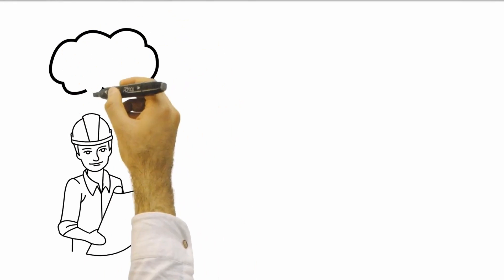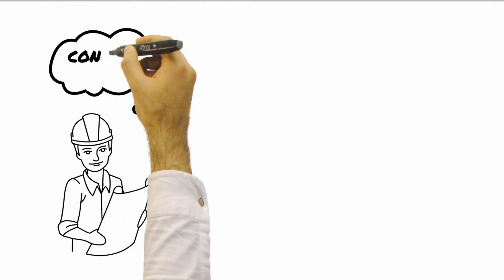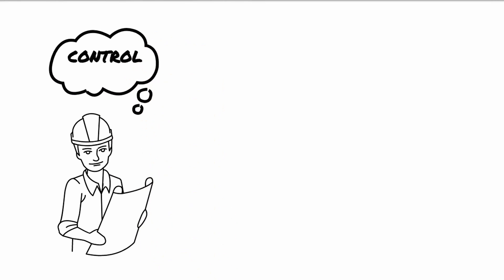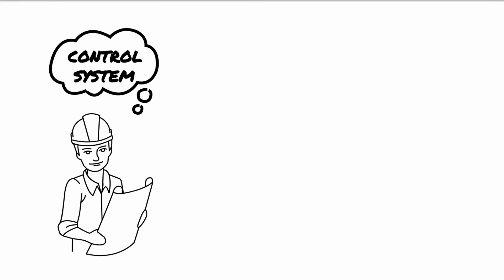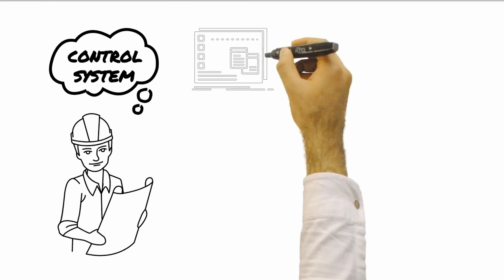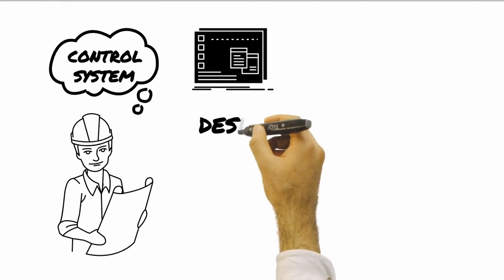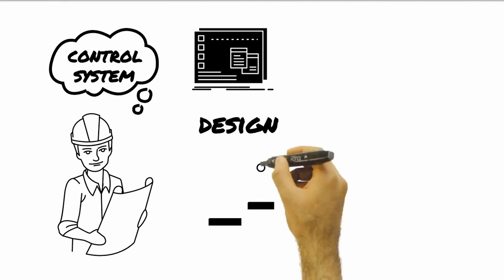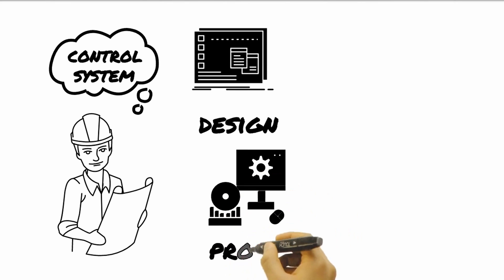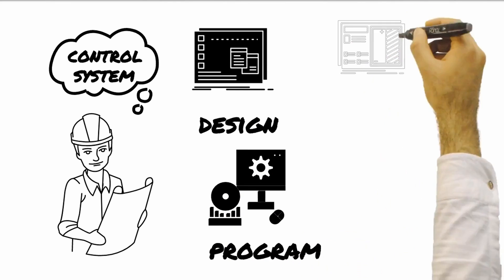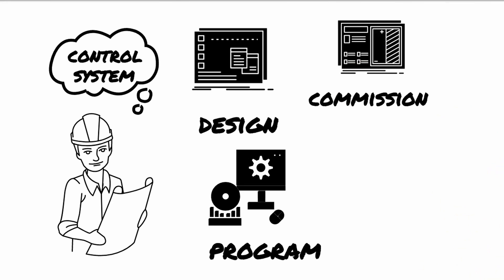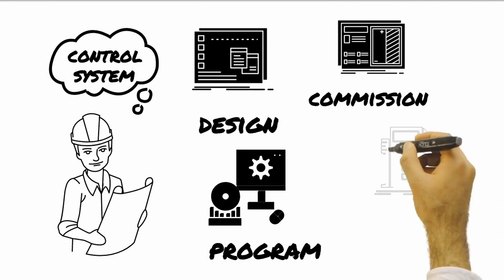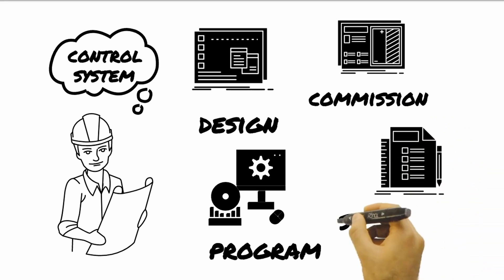HVAC controls or controls in general are basically a system that tries to duplicate the thought of the system designers. Because the system designers are not probably the one who will make the detailed design nor who will program or commission the system, his or her thoughts and ideas of how the system should work must be clearly conveyed. This is done through a written control sequence, also called sequence of operation.